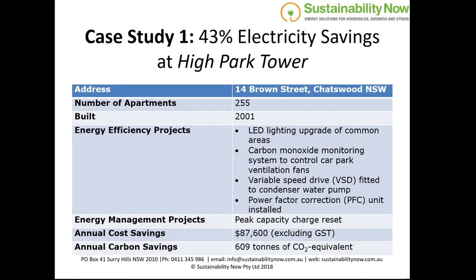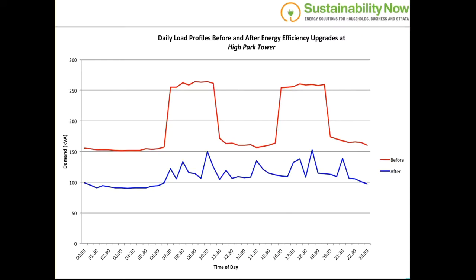They put carbon monoxide sensors in to control their car park ventilation fans. They were 75 kilowatt fans - 175 kilowatt supply and 175 kilowatt exhaust. You can see here the car park exhaust fans running in the morning. So putting on the carbon monoxide sensors, the load went down to this sort of profile.